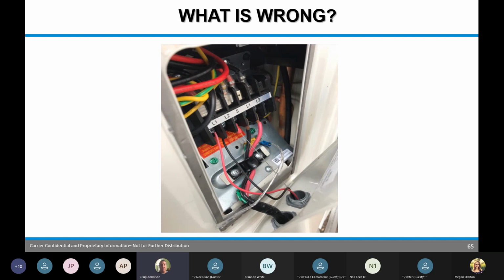Here's a big one as well when you guys are out there. If you're getting communication issues, look at your environment. If it's computer rooms, stuff like that, look at what kind of wire they used. We want 14-3 stranded wire. This is a communicating cable. It's like computers, it's like speaker wire. We get better communication through a braided wire. So make sure they've run the proper wire. This one here, it looks like they've used a low voltage wire, and we're not sure what they've used on the signal wire itself. So be very mindful of the wire that the person has used if we're getting error codes and stuff like that.